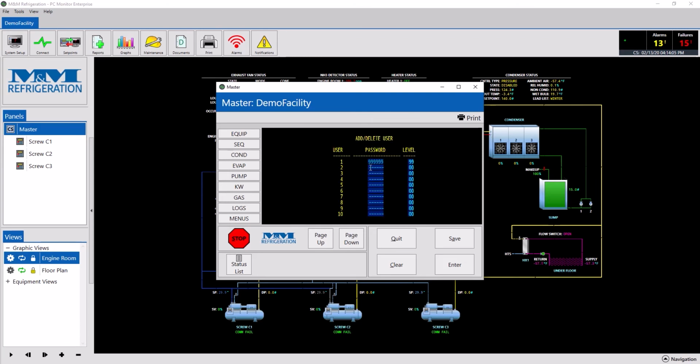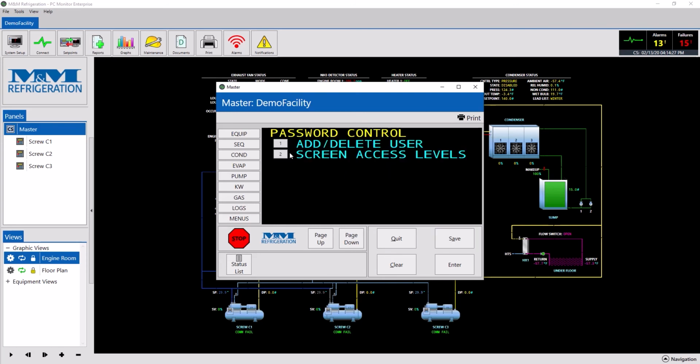You can add up to 10 unique users with their own password and access levels. A default user is in the system with a read and write level of 9. I'm adding an account now with read and write levels of 5, and another account with complete read privileges at 9, but a write level set to 0, meaning that they can't change data. This gives us one account with supreme access and two with varying levels of access.